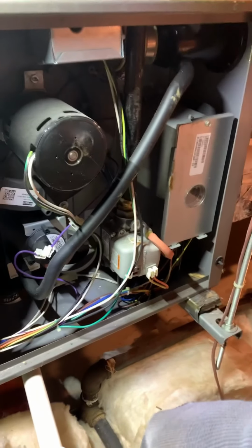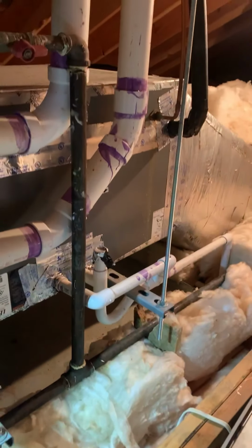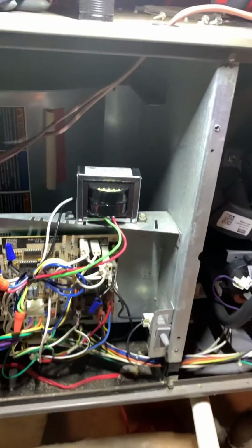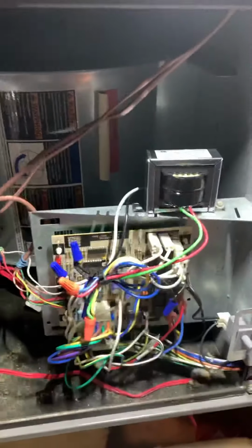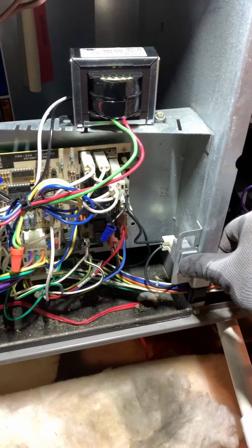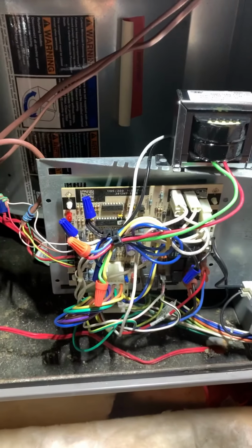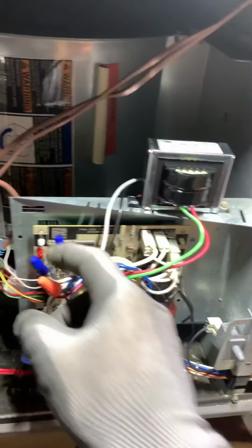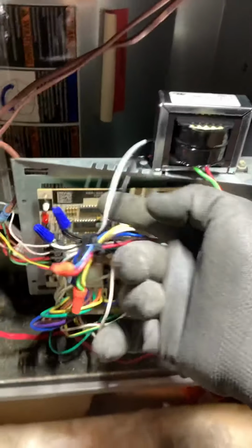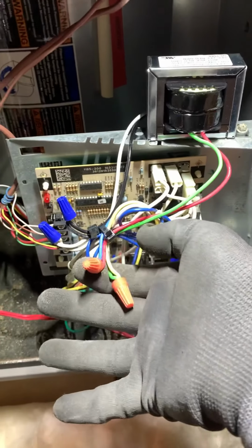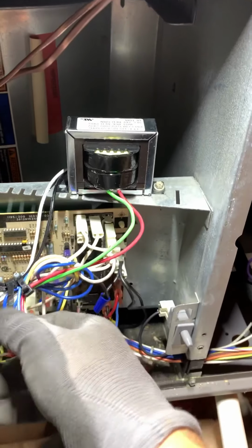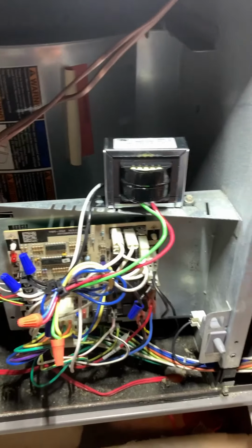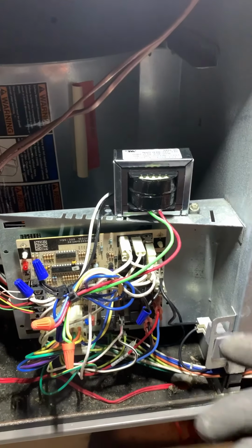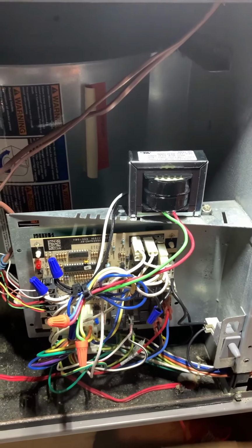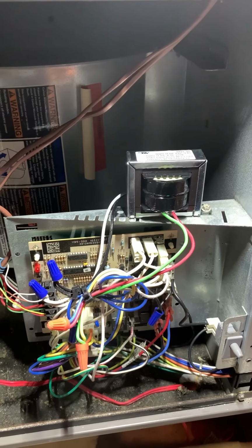It's September 10th. We have a Lennox gas-fired furnace with an AC coil on it. It's the end of the summer and we got no power going to the board, even when you push the safety door switch, no power at all. I'll show you, we've got power coming in right here to the transformer, but no power coming out. So that leads us to the transformer, which we did change last year. We've got to see why this popped again. Could it be a bad transformer? Sure, but maybe it's a sticky contact on the contactor downstairs.